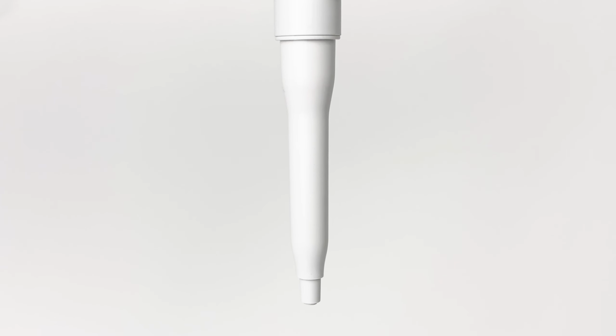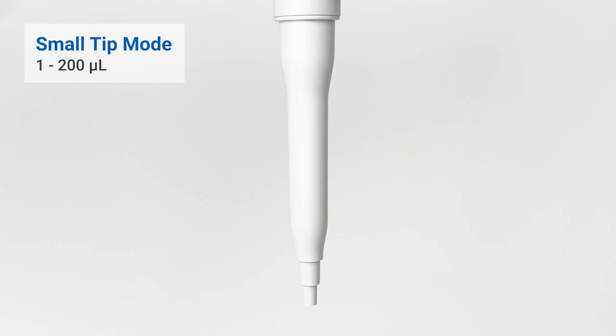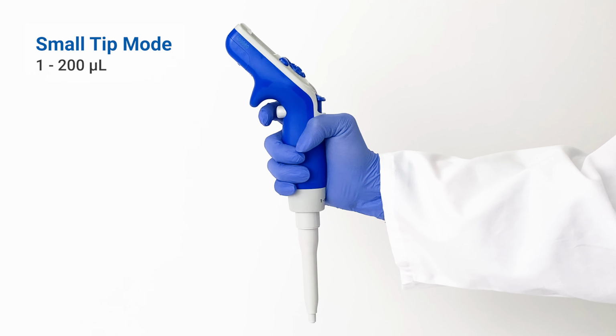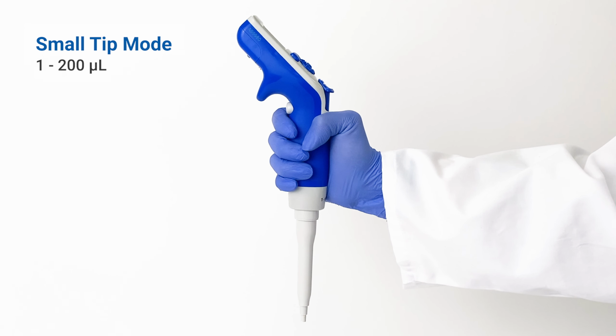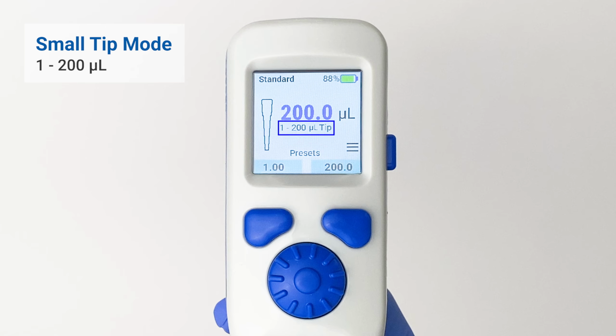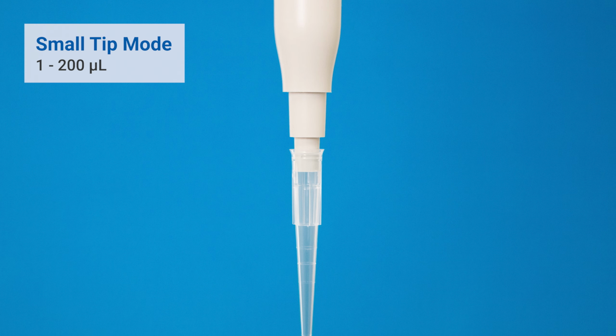To pipette volumes between 1 and 200 microliters, activate small tip mode by pressing the trigger button until it clicks. On the screen, 1 to 200 microliter tip will be displayed along with the small tip mode tip status icon. The tip selector at the bottom of the device will look like the picture displayed here.